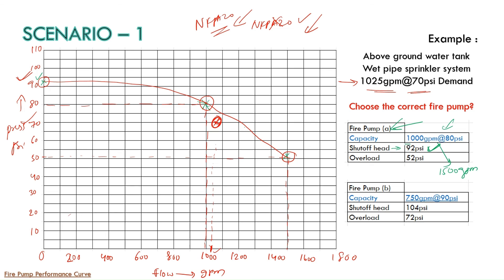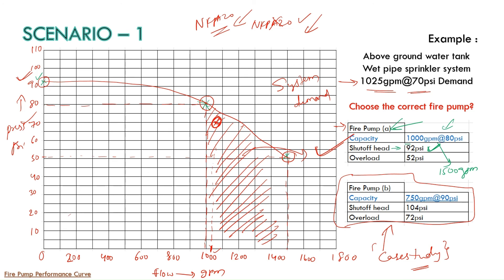So here you have 70 PSI and 1025 GPM. So this particular system demand is inside this performance curve. So this pump is acceptable and we can consider this particular fire pump in our project. However we have fire pump B as well. I hope you understand the concept. So this you can take it as case study and let me know whether this fire pump can also be selected in our project or not.